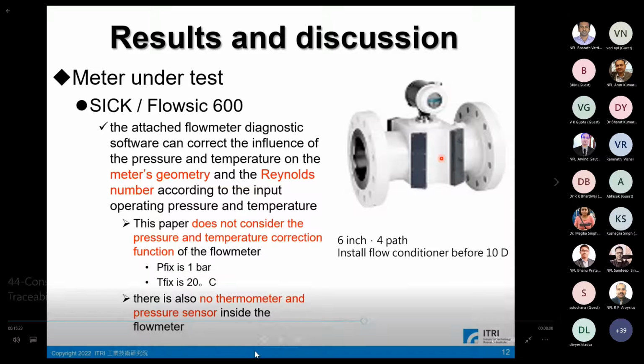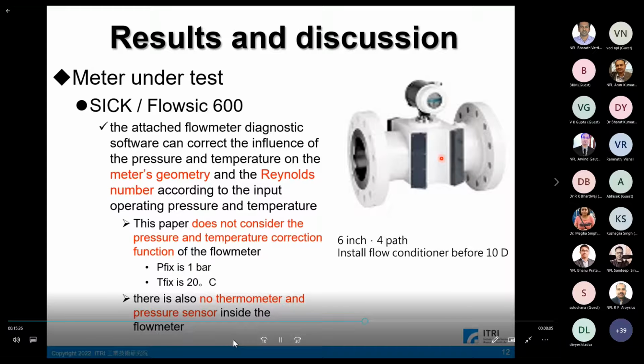The diagnostic software can correct the influence of the pressure on the meter's geometry and the Reynolds number according to the input operating pressure. This paper does not consider the pressure correction function of the flow meter, and there is also no thermometer and pressure sensor inside the flow meter. The pressure value P fix is directly fixed at 1 bar, and the temperature value T fix is fixed at 20 degrees Celsius, and then we perform the calibration.